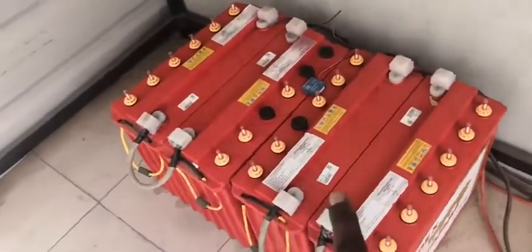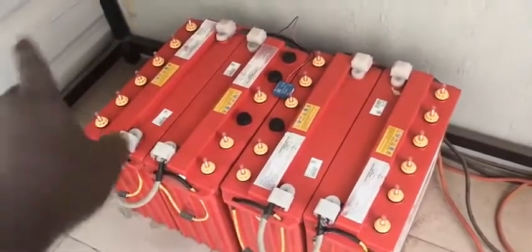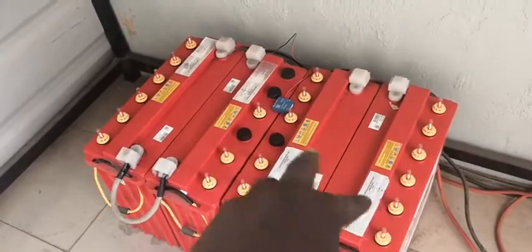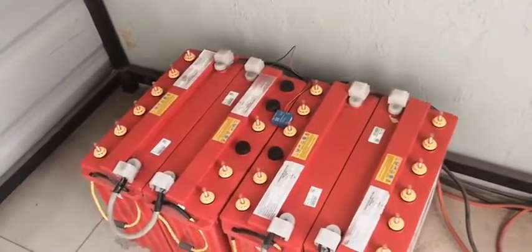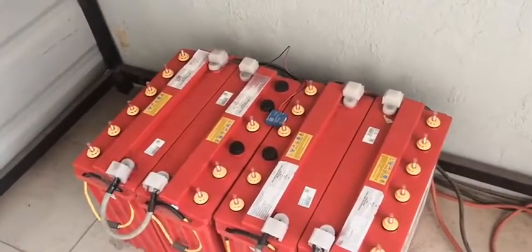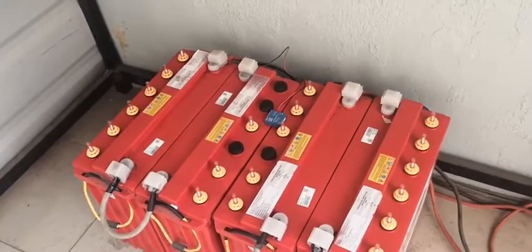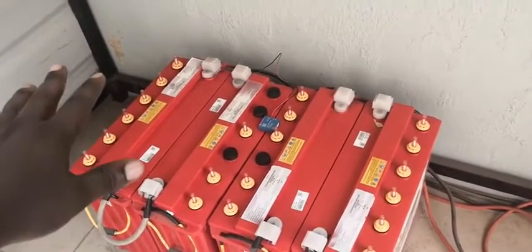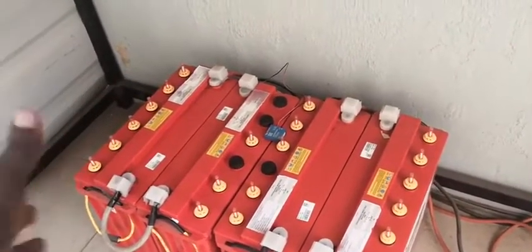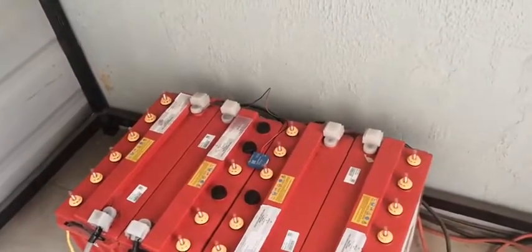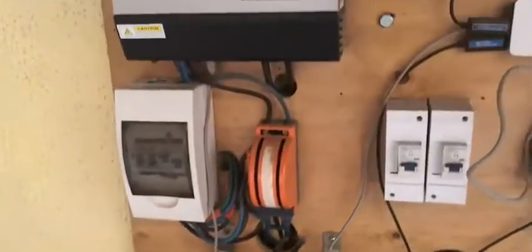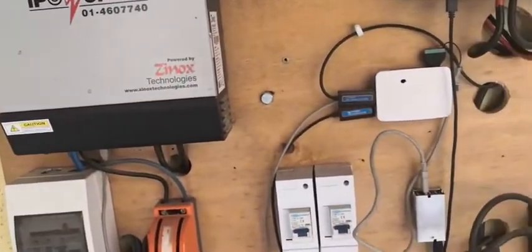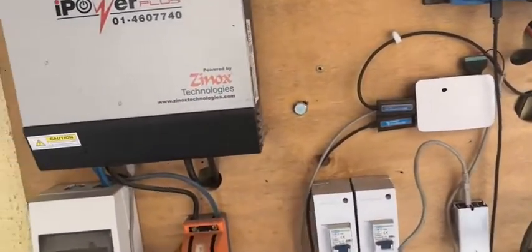These batteries are connected series-parallel, so you have 24 volts, 24 volts, then I parallel the output. For the capacity test, I decoupled them, paralleled them, and ran a capacity test on one bank and then on the other bank, and they held their own. I just finished carrying out some maintenance, charging, equalization, and whatnot.